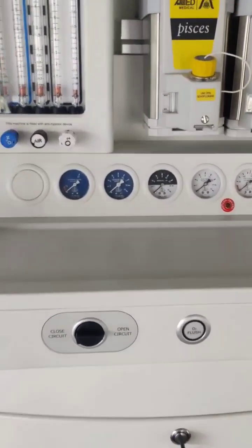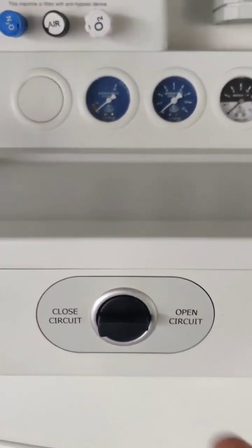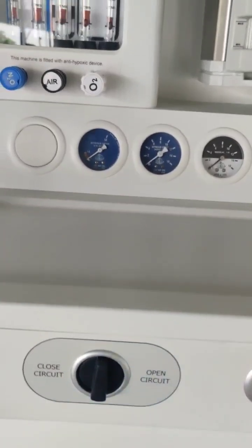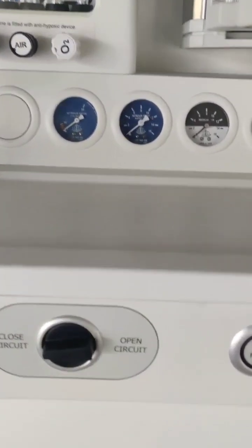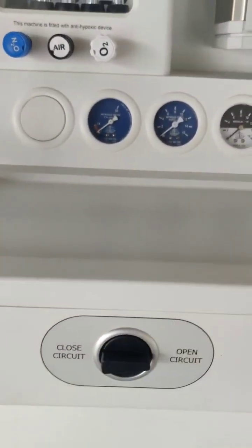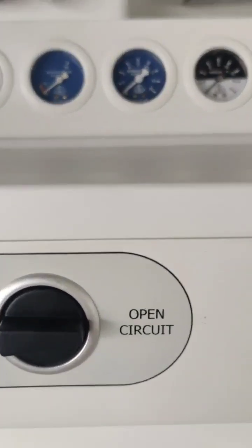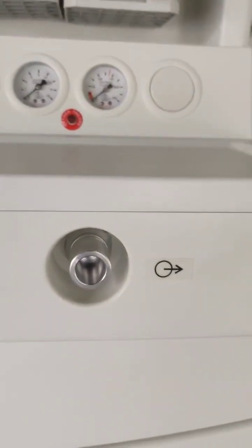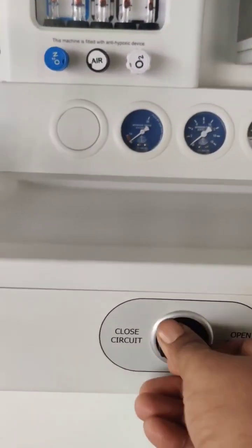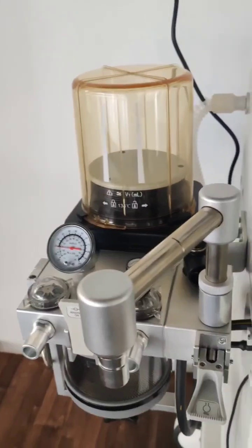At the front itself we are giving the changeover switch, which is to take the output of the anesthesia gases. Either you can take it from the open circuit or from the closed circuit. As soon as you put it on the open circuit, ACGO will get activated, and as soon as you put it back to the closed circuit system, the gases will start flowing to the breathing module over here.